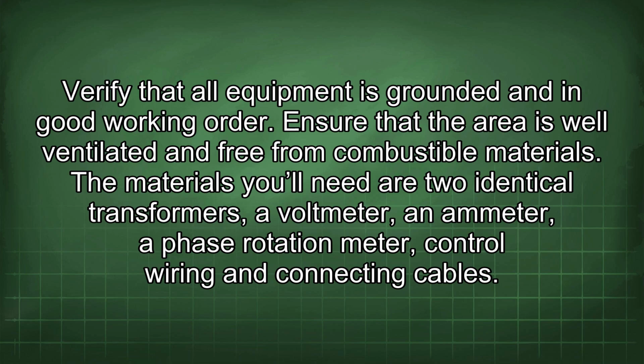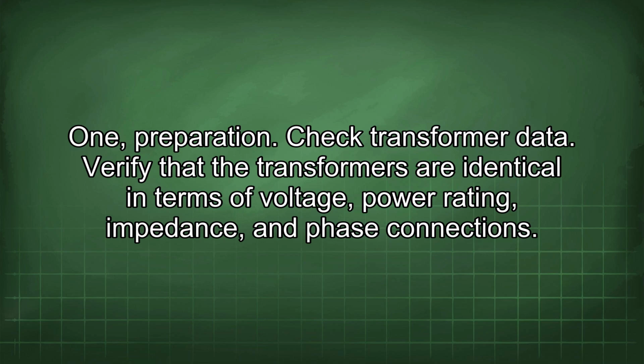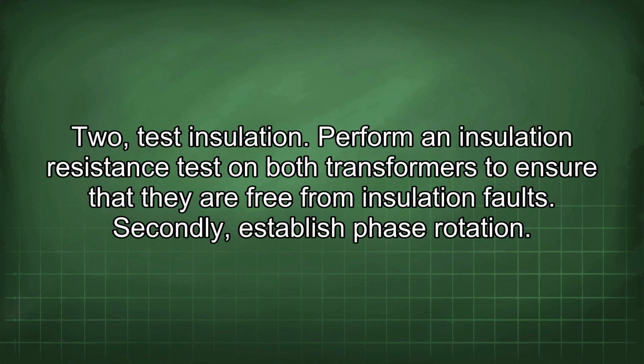The materials you'll need are two identical transformers, a voltmeter, an ammeter, a phase rotation meter, control wiring and connecting cables. 1. Preparation. Check transformer data. Verify that the transformers are identical in terms of voltage, power rating, impedance, and phase connections. 2. Test insulation. Perform an insulation resistance test on both transformers to ensure that they are free from insulation faults.